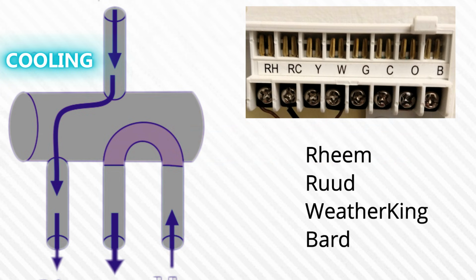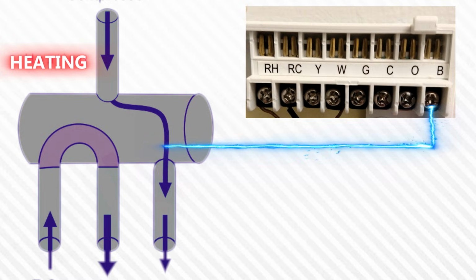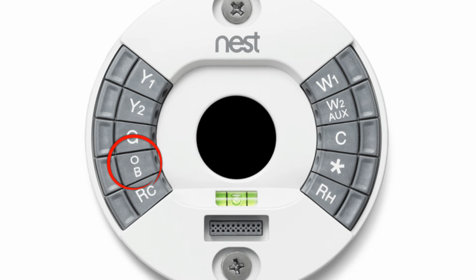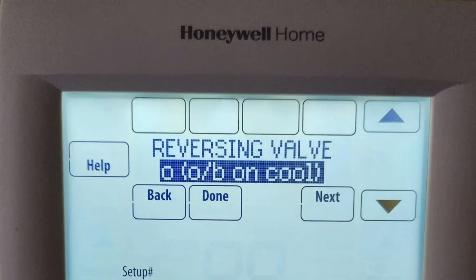Now, for systems that have a valve that defaults in the cooling position, we have to send out 24 volts to change it over to a heating position, and that's what the B terminal is for. Thermostats that combine both of these terminals together, especially the new smart thermostats, are going to take you through a setup process that will ask you when to energize this particular terminal. If your system defaults in the heating position, you want to energize it on cool, or O. When it defaults in the cooling position, you want to energize it on B.